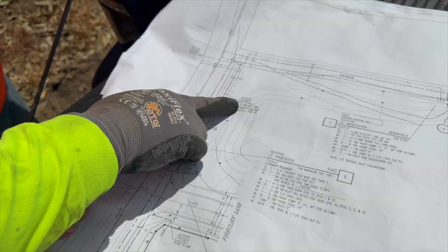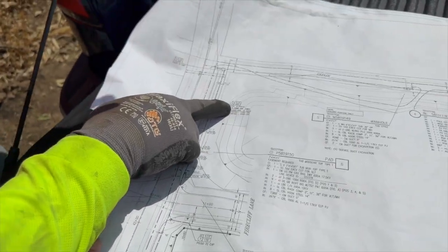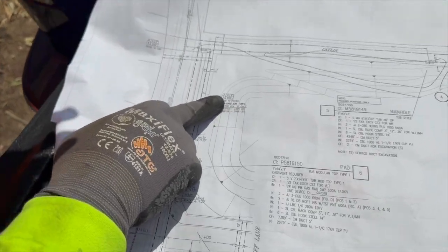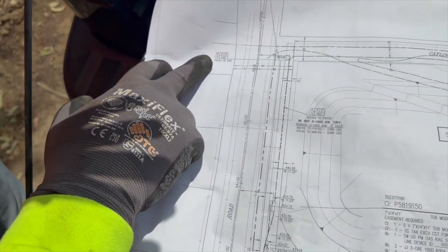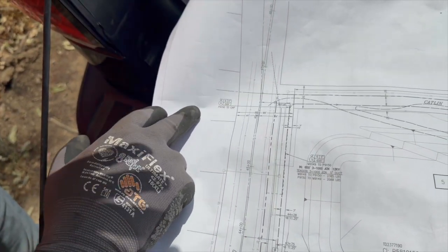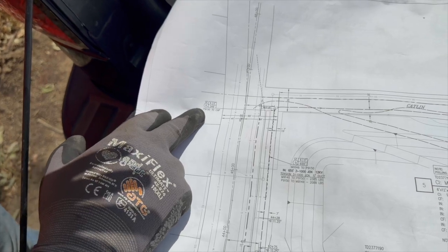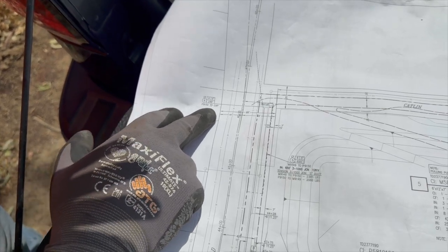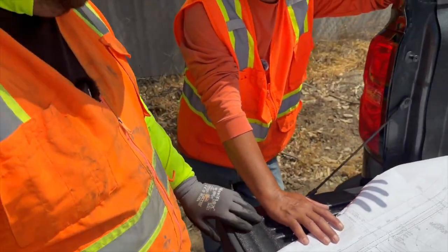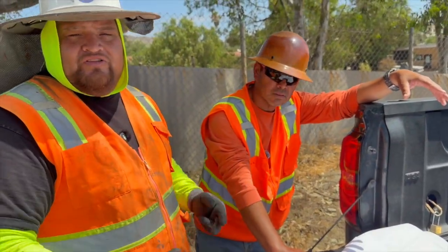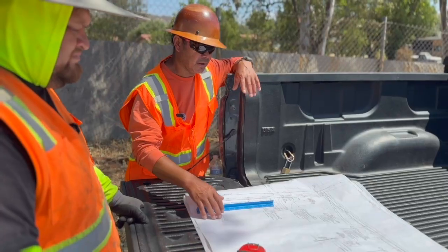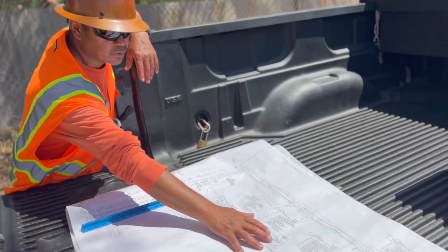If you see here, it shows call out number 5 for the six 5s that I previously mentioned. Now you go to the call out on the left hand side, it'll show six 5s, 249 feet from pad to the cap. So that's going to be a future cap. Yeah, cap means future conduits that are being stubbed out that are going to be used later on. Okay. So we have a couple more call outs right here.